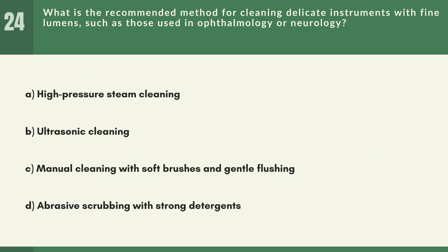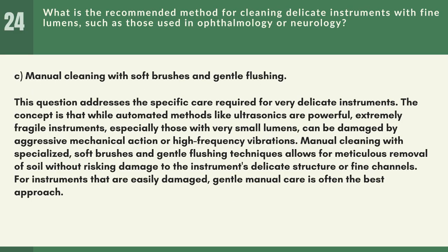Question 24. What is the recommended method for cleaning delicate instruments with fine lumens, such as those used in ophthalmology or neurology? A. High-pressure steam cleaning. B. Ultrasonic cleaning. C. Manual cleaning with soft brushes and gentle flushing. D. Abrasive scrubbing with strong detergents. Answer: C. Manual cleaning with soft brushes and gentle flushing.